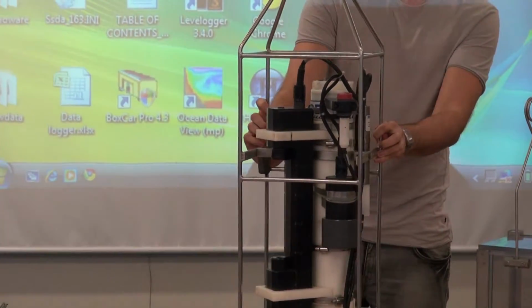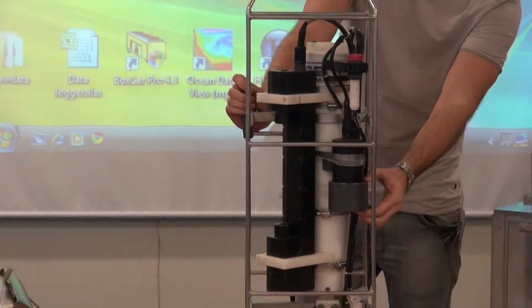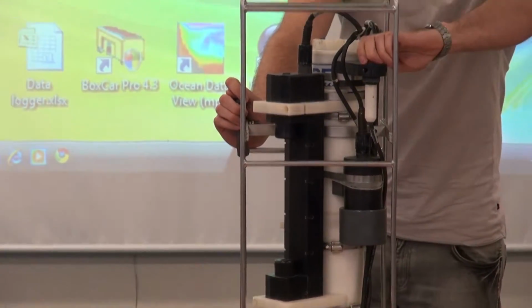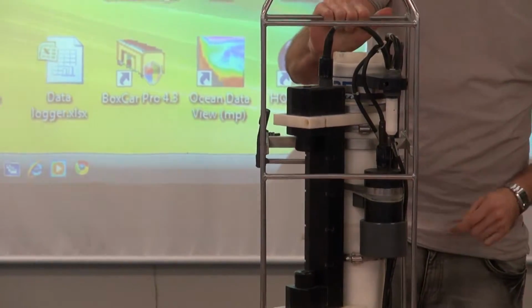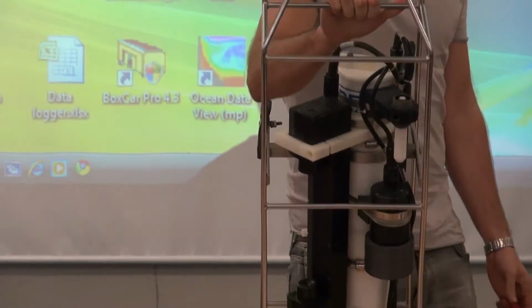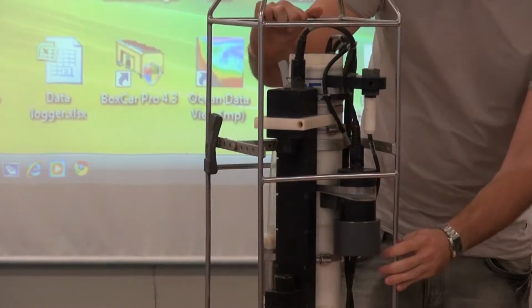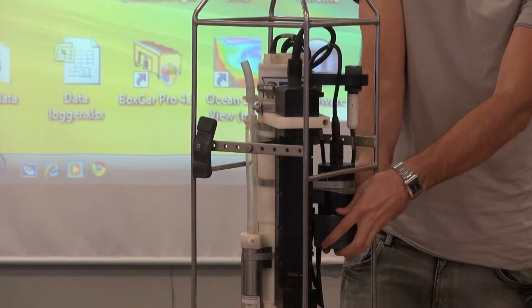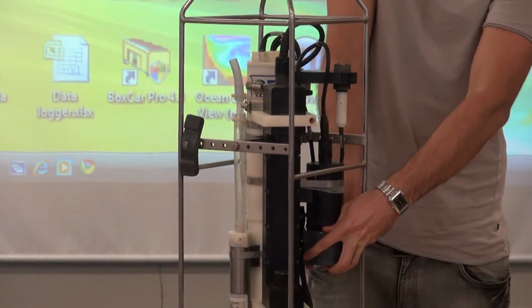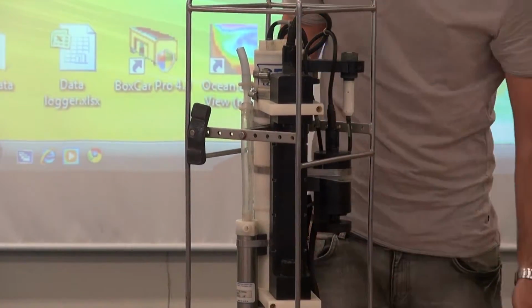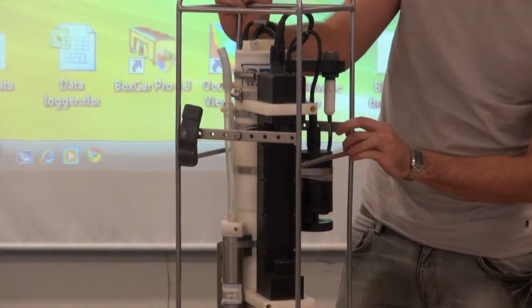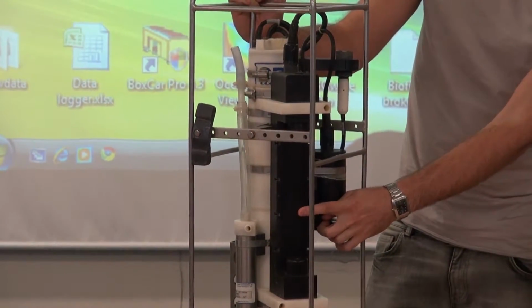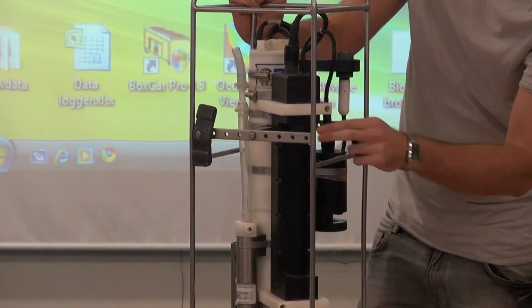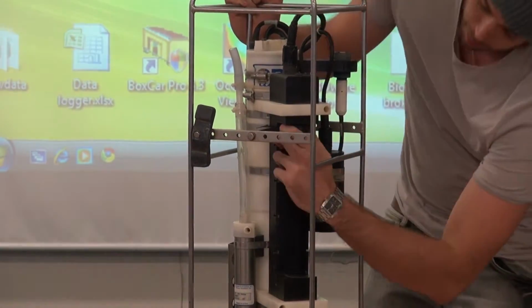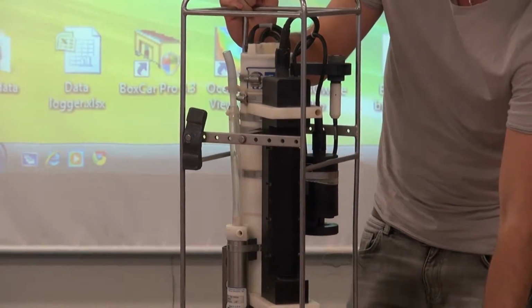On the older instrument, we don't have a pH sensor. We do have a chlorophyll fluorometer. We've got a PAR sensor up the top here, photosynthetically active radiation. That's got a cap on it usually, which needs to be taken off. Fluorometer has a cap too, which is a bit of a pain. And we've also got a beam transmissometer, which has a cap on either side, which measures water clarity.